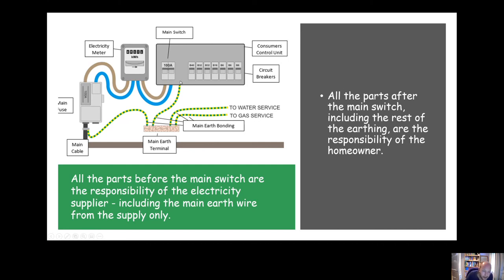There are a few parts of the earthing worth noting. The main earth terminal should be connected to the earth bar in the consumer unit, to any structural metalwork, to your water supply as it comes into the property, and to your gas supply within 600mm of the gas meter.